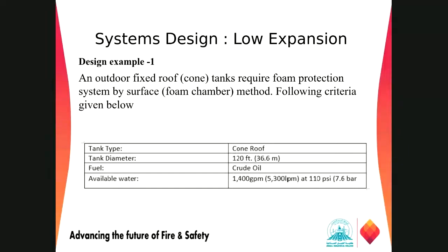So we have a scenario here, right? Outdoor fixed cone roof tanks. And we know we need foam protection for that system, which is a surface foam chamber. From the top, we will apply foam onto the system to extinguish the fire. The tank type is the cone roof. The diameter is 120 feet, big tanks, and the fuel storage is crude oil.